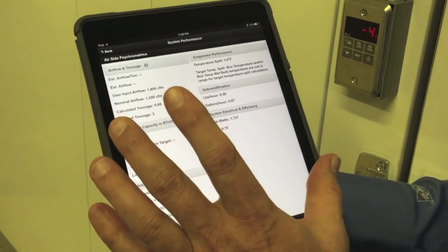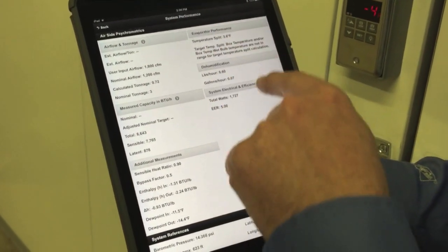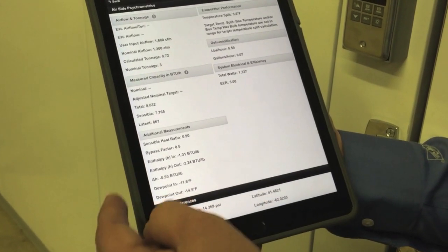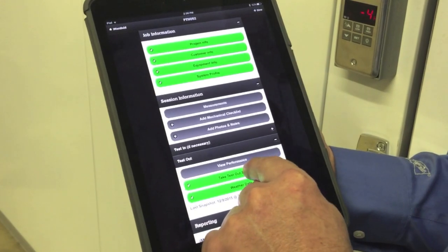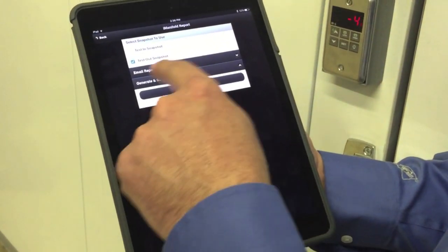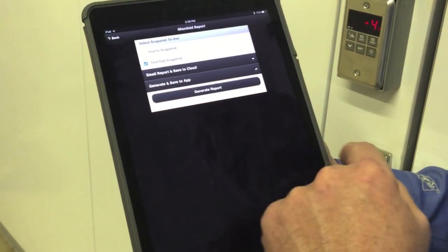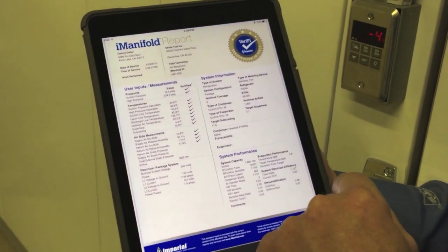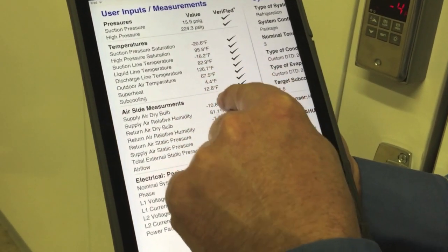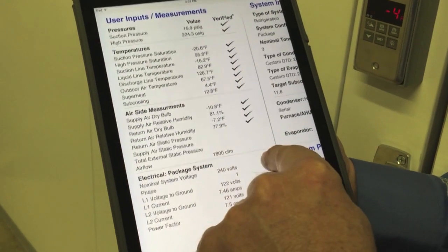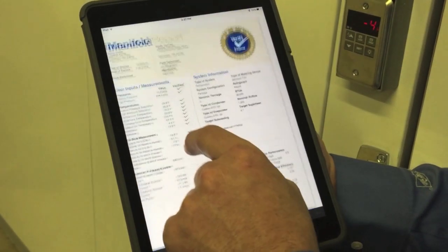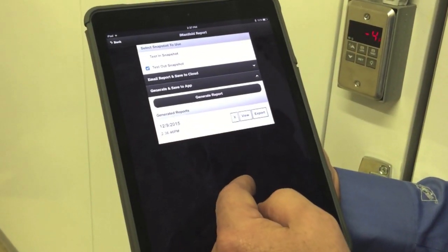There's not a lot on performance because this is a refrigeration system, not an air conditioning system. We can see our temperature split in the box, our dehumidification, our EER, dew point in and out, some other basic information along with elevation and other performance indicators. We can take another test-out snapshot if we'd like — it'll overwrite that snapshot. Now we can generate a report. The iManifold report is our free report. You can do a report for test-in or test-out. In this case we only did a test-out snapshot, so I'll generate that report. You can see right away that the readings are verified, meaning these readings came off the tool — pressures, corresponding saturation temperatures, supply dry bulbs and wet bulbs, and other information about system performance. This allows you to very quickly generate a commissioning report for your customer so they know the system is operating the way it's supposed to.